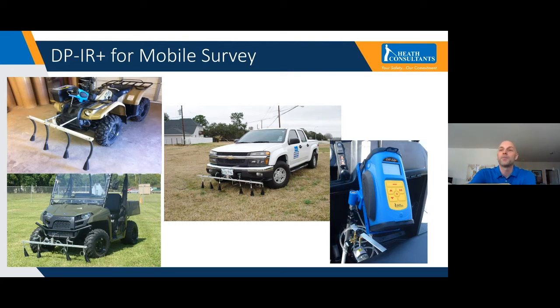I know that we made some changes to our mobile kit about 5 or 6 years ago. So I would recommend reaching out to your respective sales consultant if you do have a mobile kit, to make sure that you have the most current and up-to-date version. The old kits utilized the cones, would go to the external pump, and then go to a flow gauge, which regulated the flow going to the instrument. We removed the flow gauge and put in what's called a dump valve. The dump valve allows the DPIR to take what it needs instead of forcing the sample on there. The benefit of that is a much faster response time.